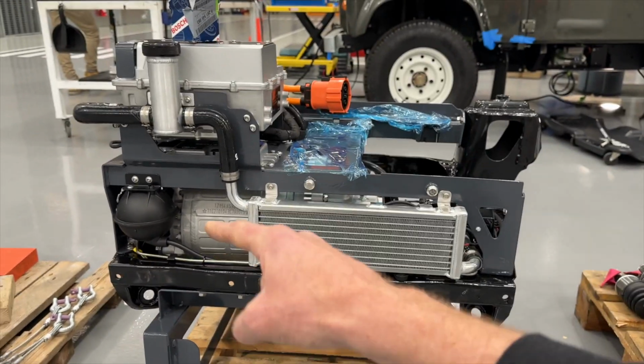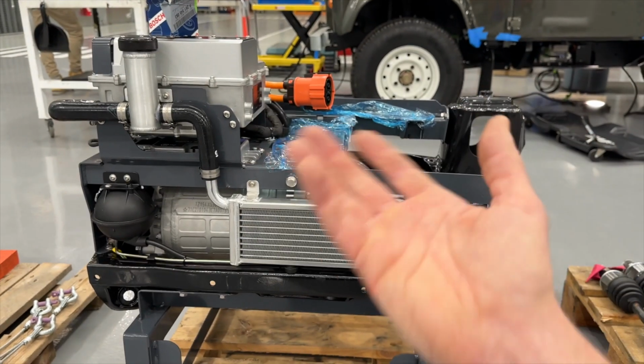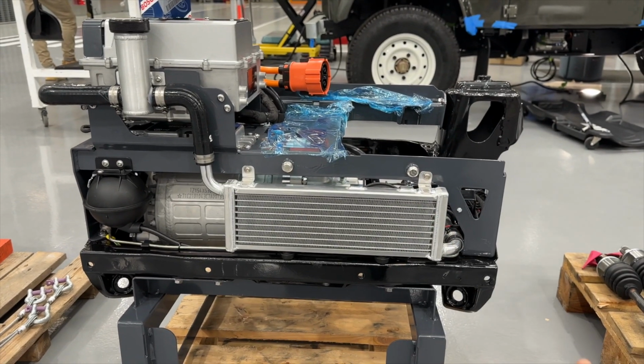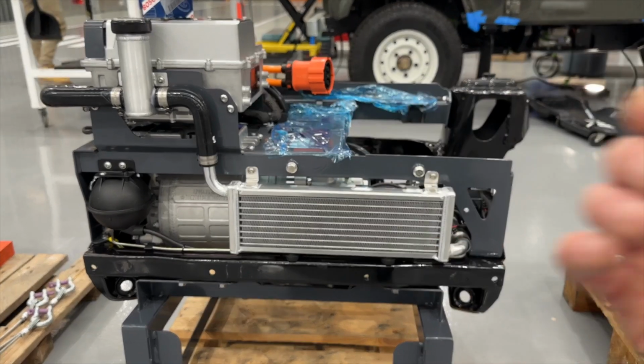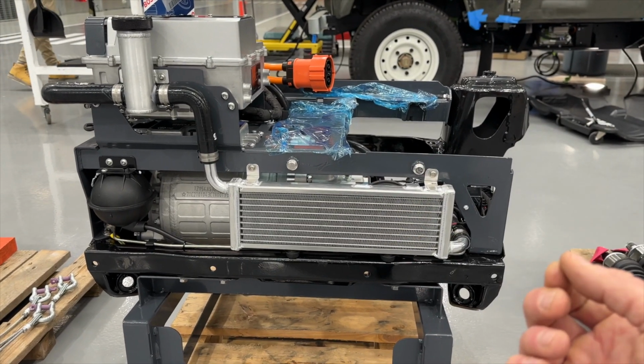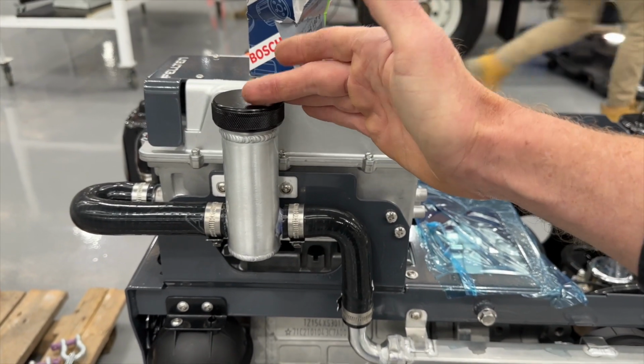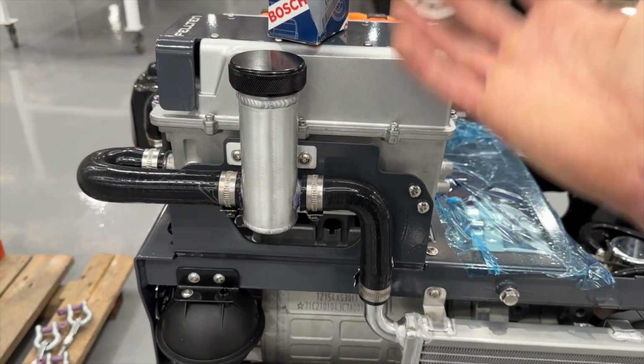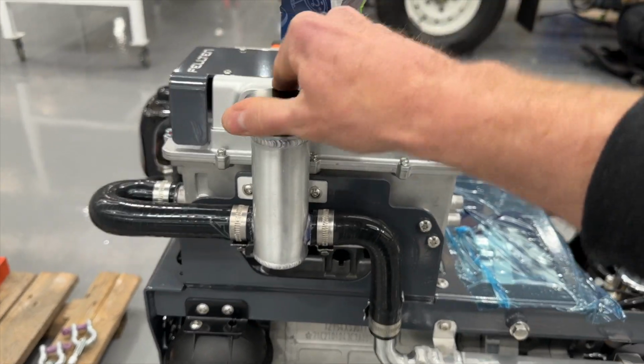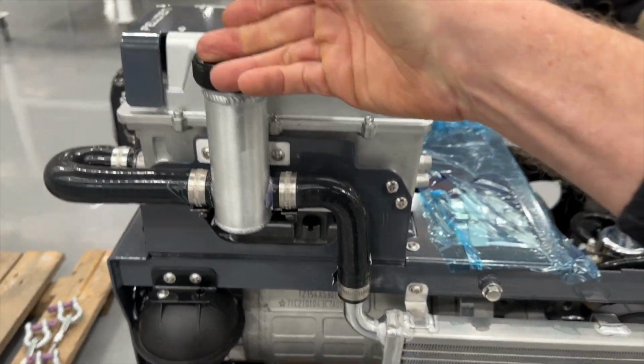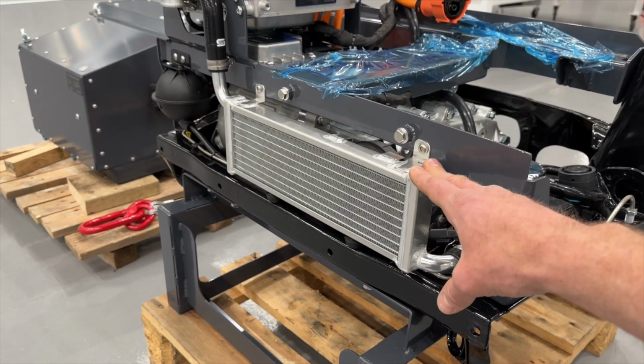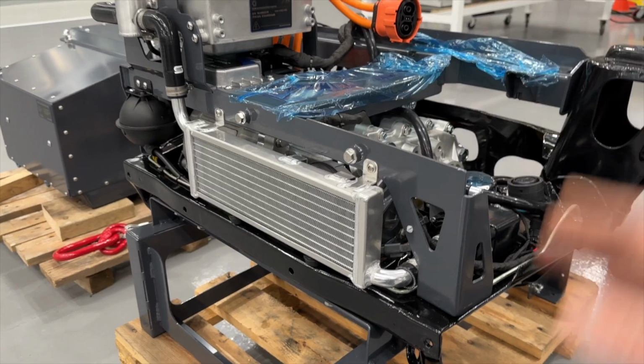It's cooling the electric motor and the inverter. Those are all running like 30-40 degrees, not very hot, just needs a little bit of cooling to keep all that under control. Because it's not running too hot, you just need an expansion tank at a high point to be able to fill. It's got a little fan on the back that we control in case we need extra cooling, but really it's just running in a nice slow speed loop.